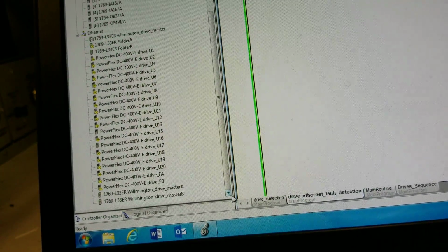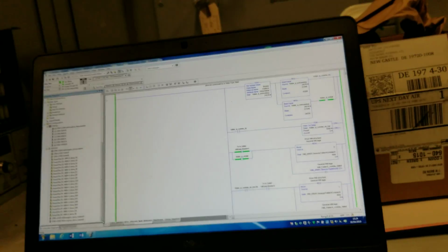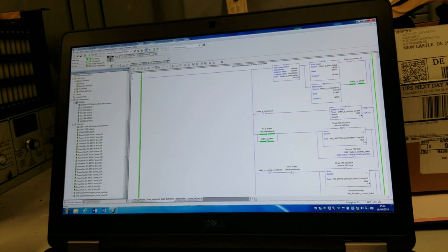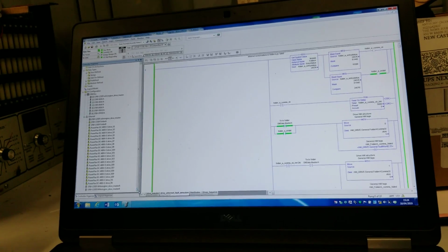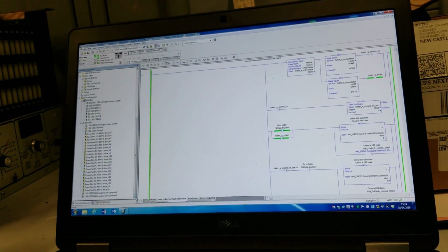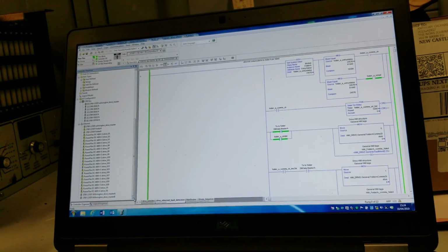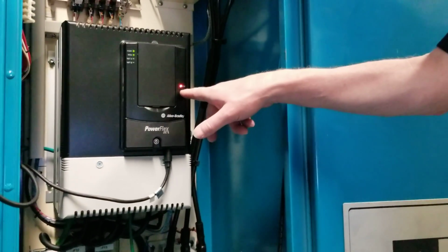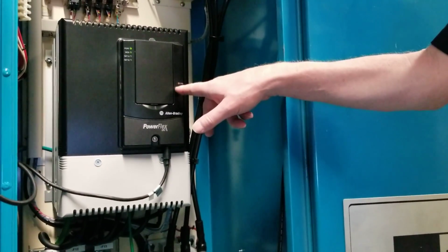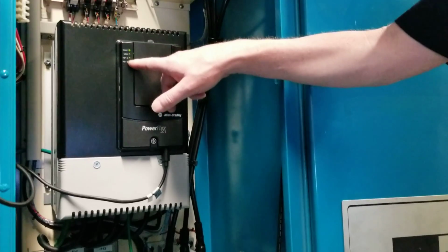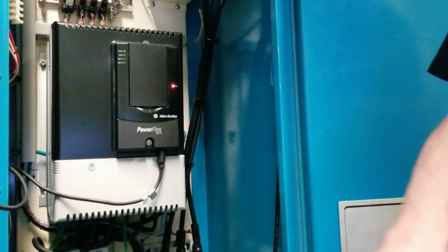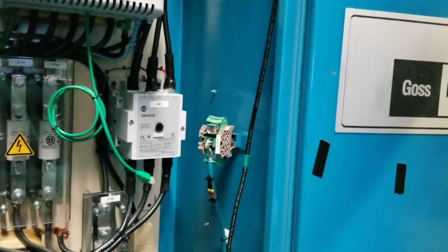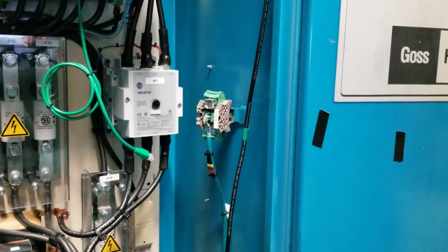Yeah. So the first thing you've got to do is find out whether it's not active, because it should be, or whether we've got this issue. Now look on the drive here. This is an important thing. Remember we talked about this yesterday. You get an orange light, and the net A and net B are not running. And that's a result of the comms master cable being unplugged. Yeah. Okay.